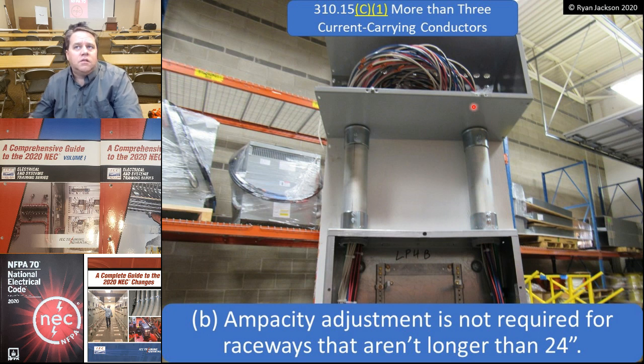We need to consider the fact, though, that a wireway is also a raceway, according to Article 100 and according to 376.2. So in this application, I would count from the top of the enclosure up to the top of that wireway. And if that distance is less than 24 inches in length, then we don't need to count the conductors in it.